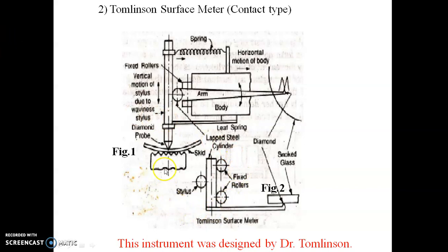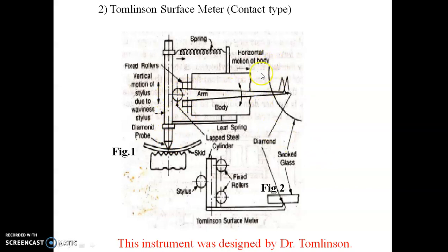In the Tomlinson surface meter, there is a diamond probe placed between cylinders and two fixed rollers. Due to the movement over peaks and valleys, it rolls up and down. The stylus arrangement is fixed by a leaf spring and connected to a helical spring, and an arm is attached to the stylus probe. When there is a peak or valley, the arm rotates up and down, recording the movement on a smoke glass dial indicator.